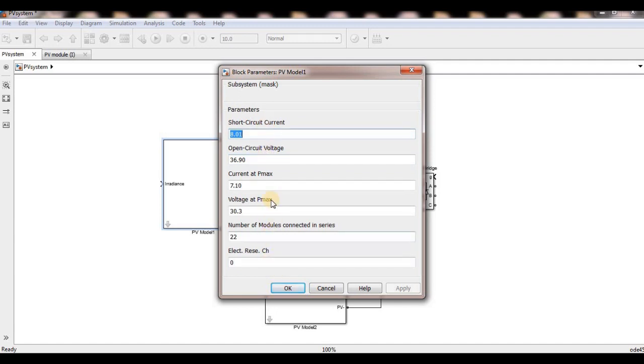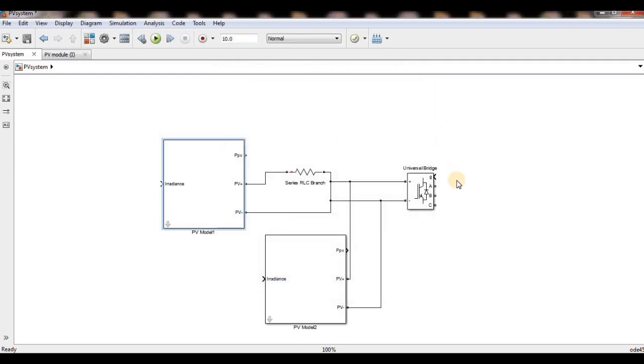With 22 or 23 modules connected, you can get 660 volts to generate 400 volts RMS of AC, so that I can connect this directly to the grid, or to a standalone system, or operate an induction motor for water pumping, or for electric vehicles or whatever.